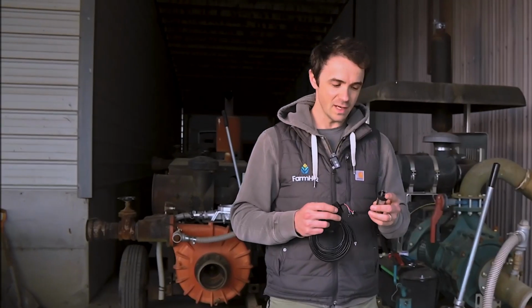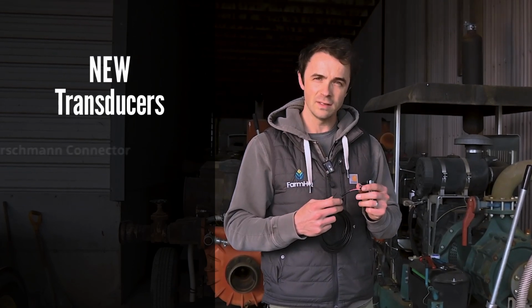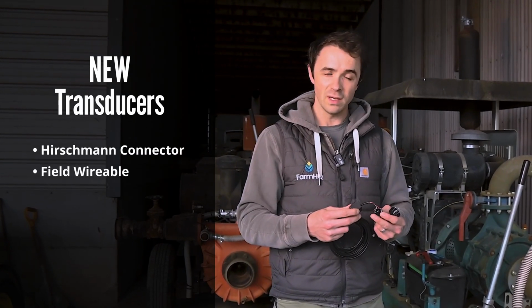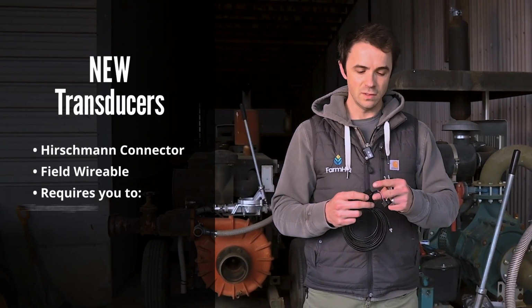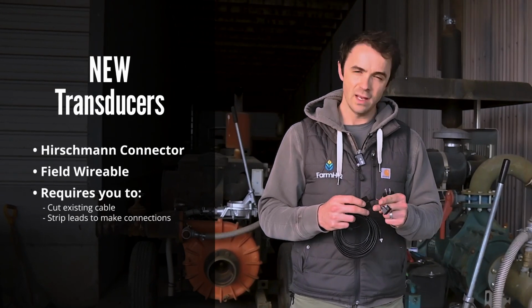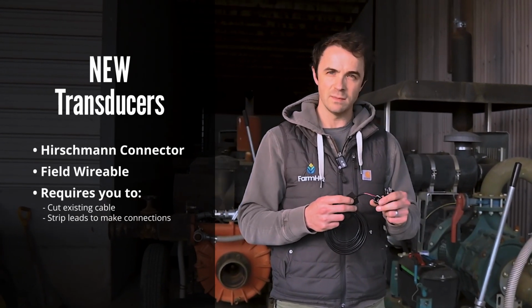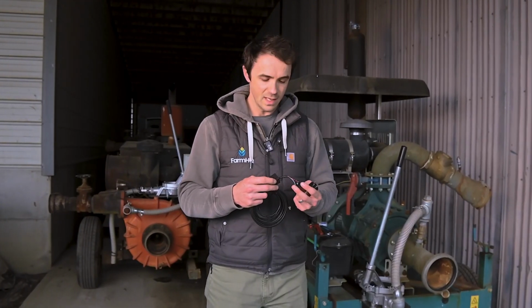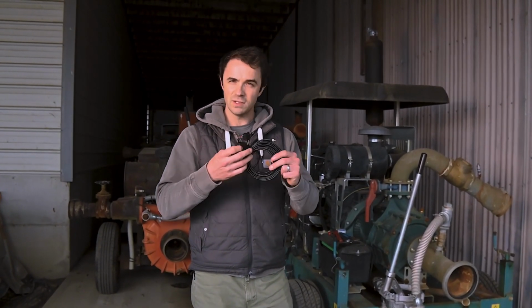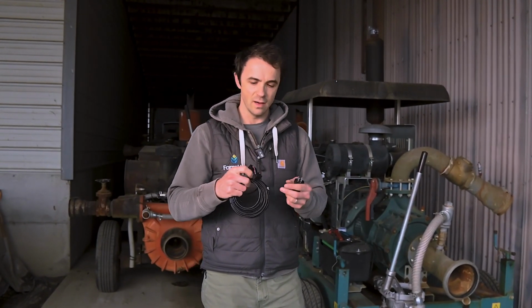These new transducers have what's called a Hirschmann connector on top. This is a field wirable connector, and it does require you to cut your existing cable and strip off the leads to make connections manually. One advantage of this is that you can cut the cable to the exact length that you need and not have a bunch of extra cable dangling around to get caught on things.